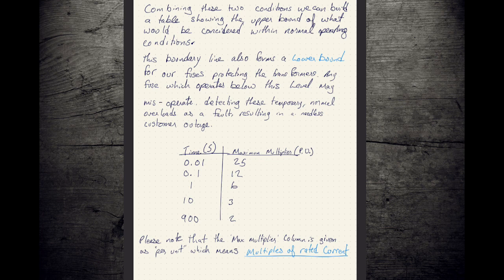That's pretty intense. Now, at the end of this period, all that magnetic back EMF, those magnetic fields, are all established. The transformer's now operating. It's doing its normal thing. Everything we see from here and down, this is loss of load diversity that we're dealing with. And after 1 second, we could be seeing 6 times the full load rating of that transformer flowing through it. Our 10 amp transformer, 1 second in, is still flowing 60 amps. That's pretty intense. By the time we hit 10 seconds, things start to stabilize.